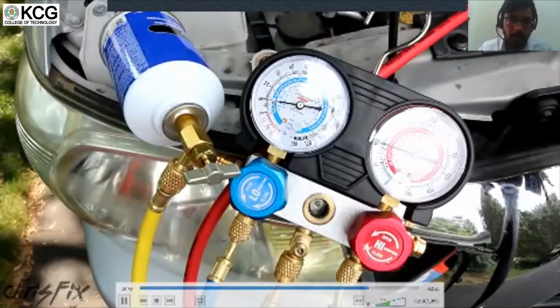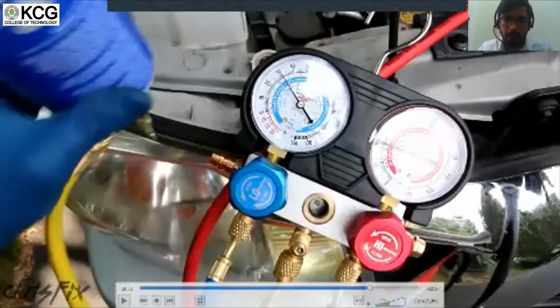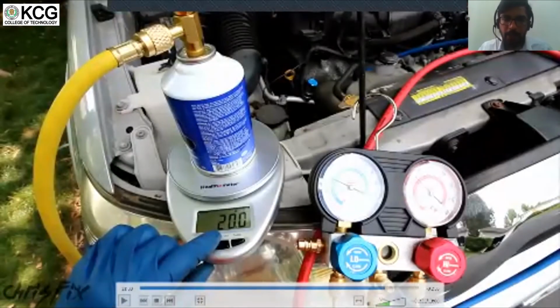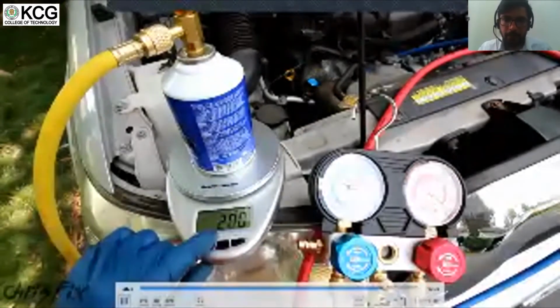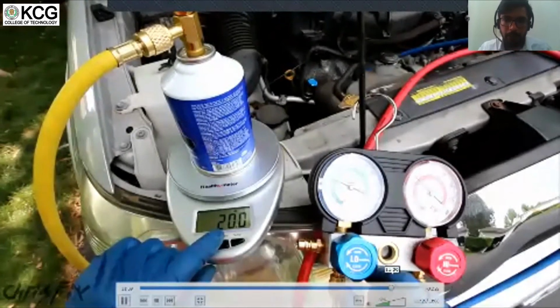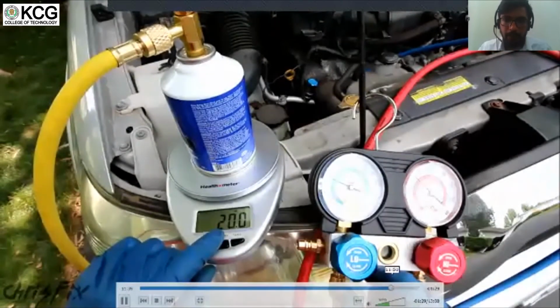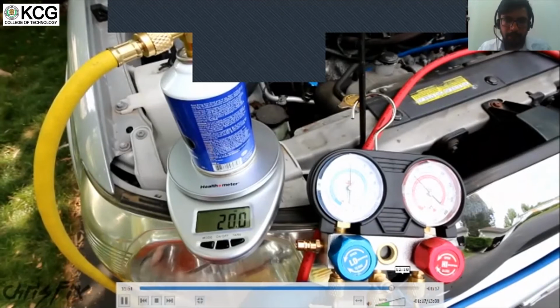So here he has converted the units from grams to ounces. So you have to see how much residual refrigerant needs to be added. We want to add 10 more ounces to the system since each can is 12 ounces, and we already added one can. Don't go all in at once because it could turn to liquid and damage the compressor. So slowly add the refrigerant.